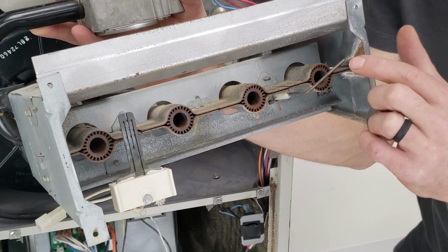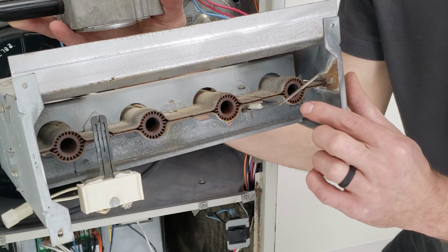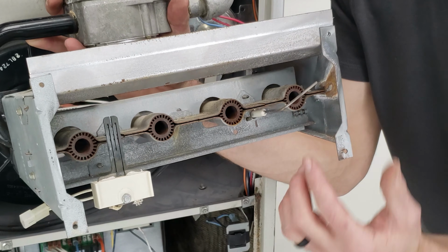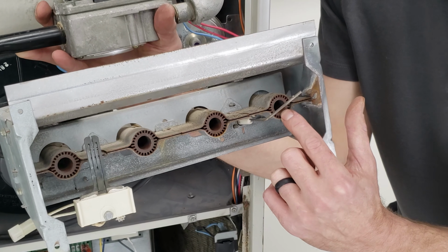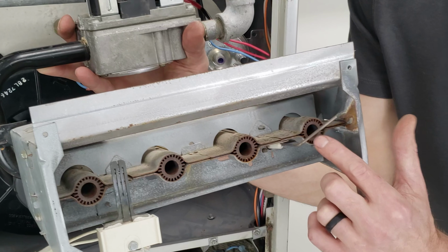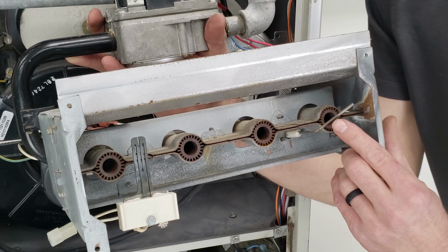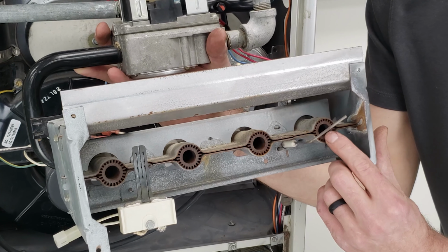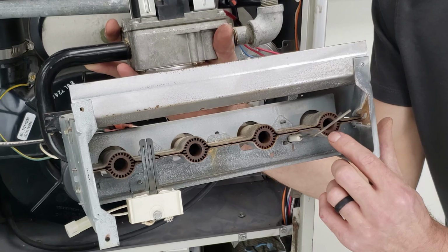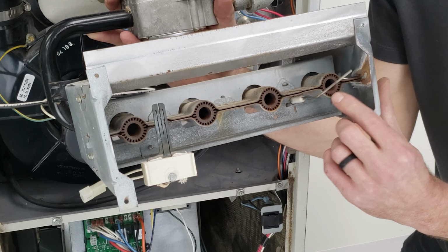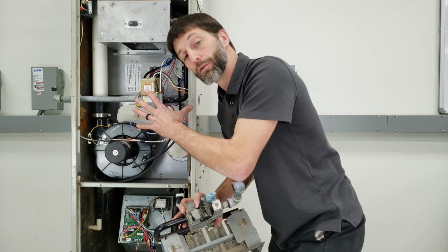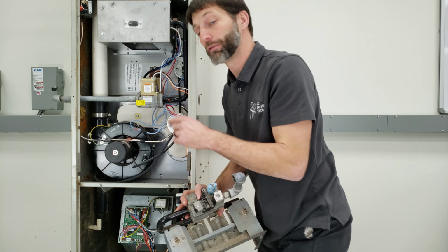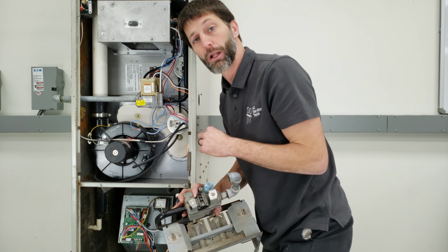There's constantly voltage on this flame rod, and what's happening is the flame rectification process is occurring, where there's a flame going from the burner retention head right here past this flame rod, and you have the power basically getting rectified, and then you're going to see a direct current. It's a microamp signal on the ground right here. And then it's a matter of having a good ground on your furnace. And so I have other videos on flame rectification down in the description section below.